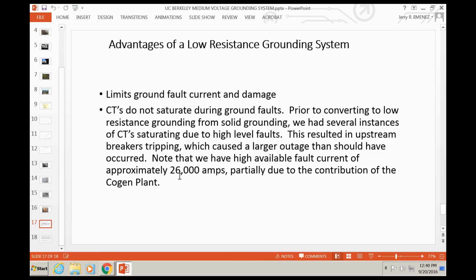And I will mention that our fault current here is a little bit higher because we have this cogen plant sitting right on our campus. Although we have large transformers, so it would be high even without the cogen plant, the cogen plant just makes it a little bit worse. Jerry, are most of your downstream substations within buildings, they have just primary switches, right? Yes. No breakers? No, at the buildings we have these fused selector switches, so they have current limiting fuses in them. Okay.